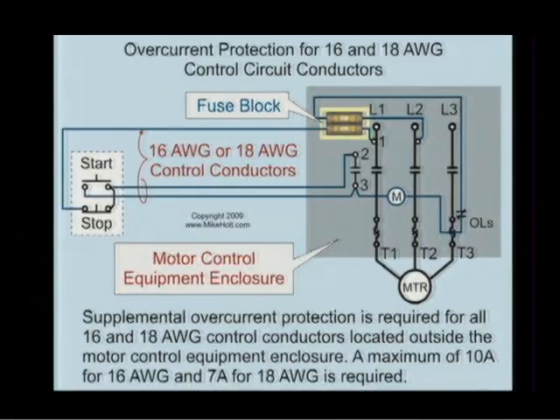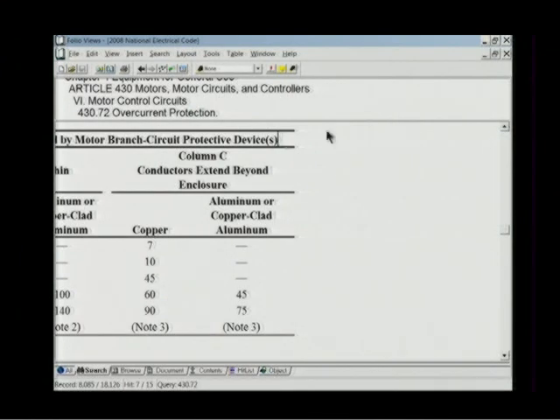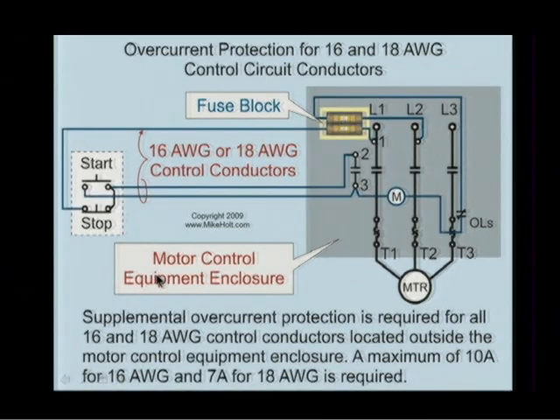Okay. So now we are making an extension away from it, but if I want to use 16 or 18 gauge control wire, and the tap that I'm making here is going to be exceeding the values given on this particular table, let's say I want to use 16 and 18, obviously, it's only 7 or 10. Then what I'm going to have to do is put a fuse block in there and provide overcurrent protection for those conductors.